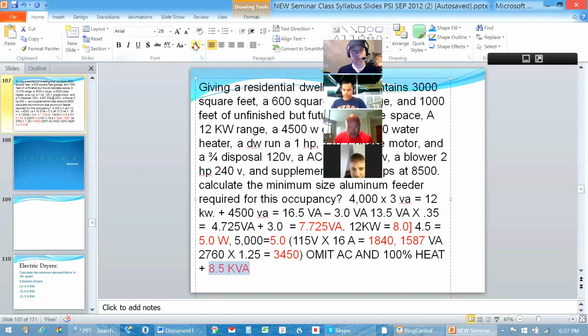All right, so we're looking at a running total here of the 7725 for the lights. We've got the 8 for the range, the 5 for the dryer, the 5 for the water heater, the 1840, the 1587, and 3450 for the motors. So plus 1.84 plus 1.587 plus 3.45. And then the larger of the two, air conditioning and heating, is going to be that 8,500, so plus 8.5. I come up with a total value of 41,102.